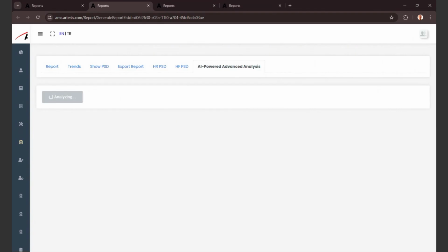I mean, the bar graph already shows, okay, there's a rotor issue which is close to red level on the bar graph. But let's see what the analysis is going to tell us. And sometimes the auto analysis might not accurately identify the severity of the problems.